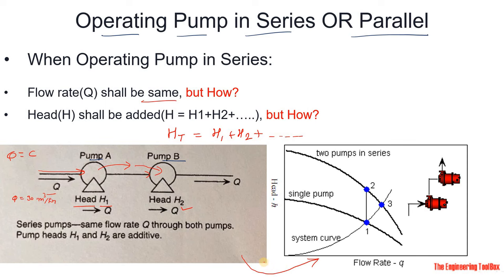Now let's understand this with a graph from the Engineering Toolbox. The curve is between head versus flow rate, and this is your system curve. When operating only one pump (pump A), this is the condition — a certain flow rate and head. When operating two pumps in series, the flow rate remains constant but the head is additive: H1 plus H2.